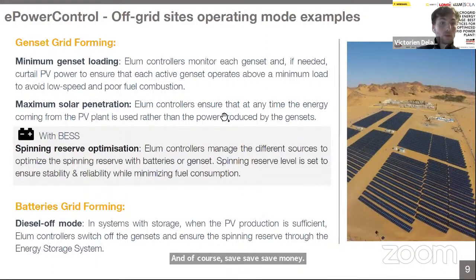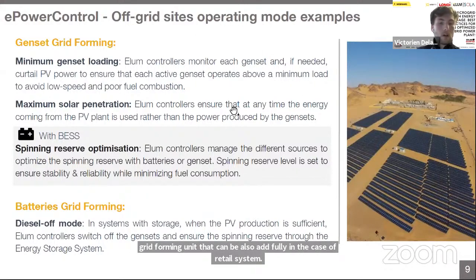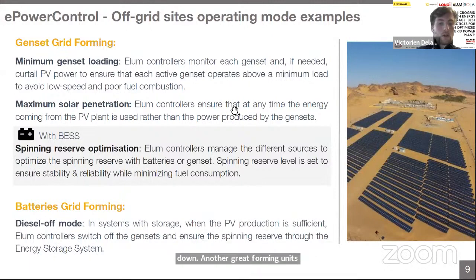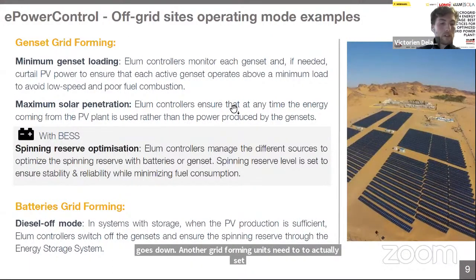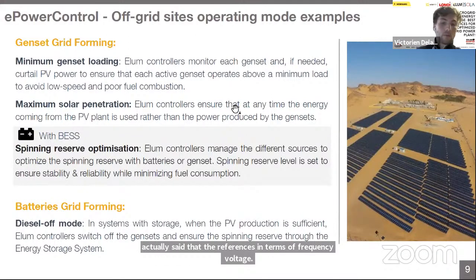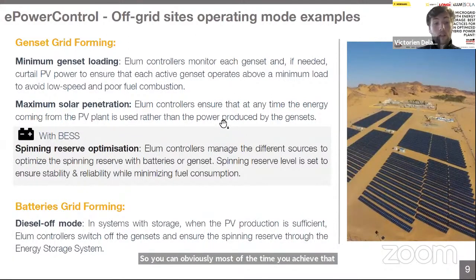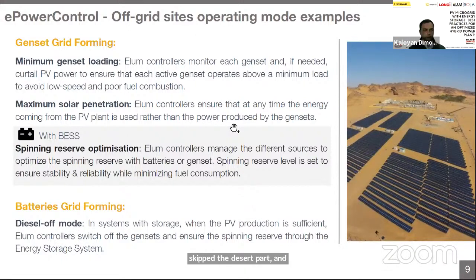You can also use your battery system as the grid forming unit. That can be helpful in the case of grid-tied systems. But as you know, when the grid is not here or goes down, another grid forming unit needs to set the references in terms of frequency and voltage. Most of the time you achieve that through diesel generators, but you can also do that through energy storage systems and batteries that act as grid forming units, to achieve what we call diesel-off mode -- totally skipping the diesel part and relying only on PV and battery.